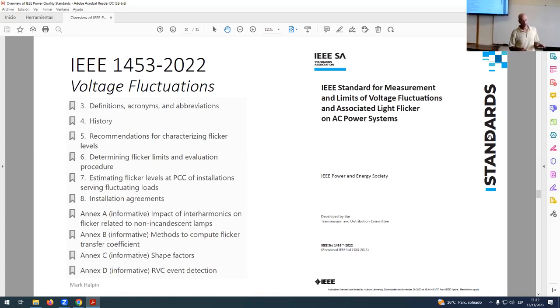That's the existing 519 as far as harmonics are concerned, and a couple of the relevant changes. What about voltage fluctuations? Well, for a long time in IEEE, we didn't have anything for voltage fluctuations. And we began to learn about the work that had been done by the International Union for Electroheat, UIE, which led to the creation of the IEC flicker meter and all the IEC flicker related standards. For a long time, we didn't have anything. We didn't want to reinvent the wheel.